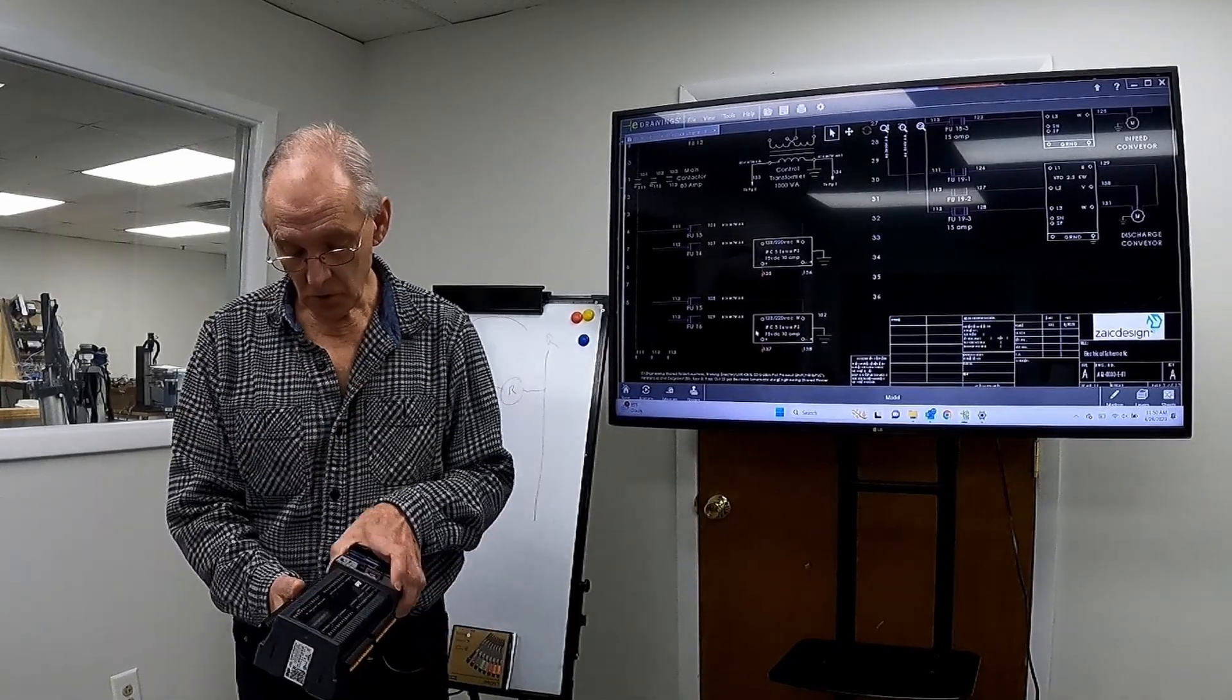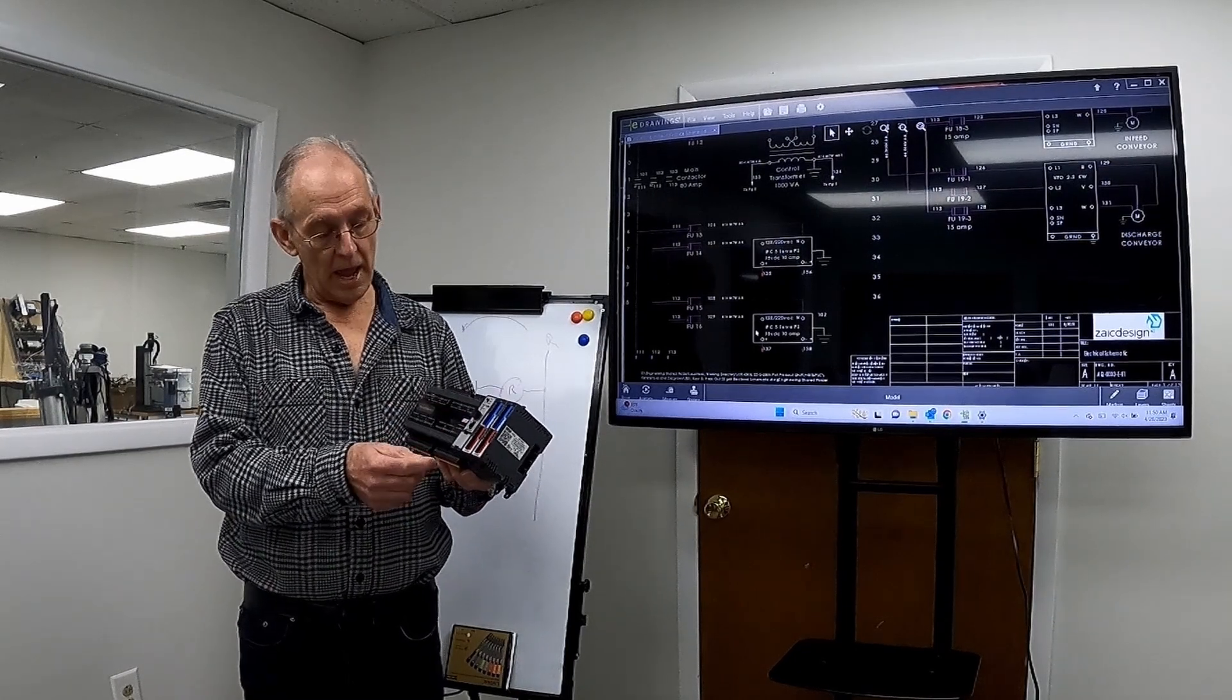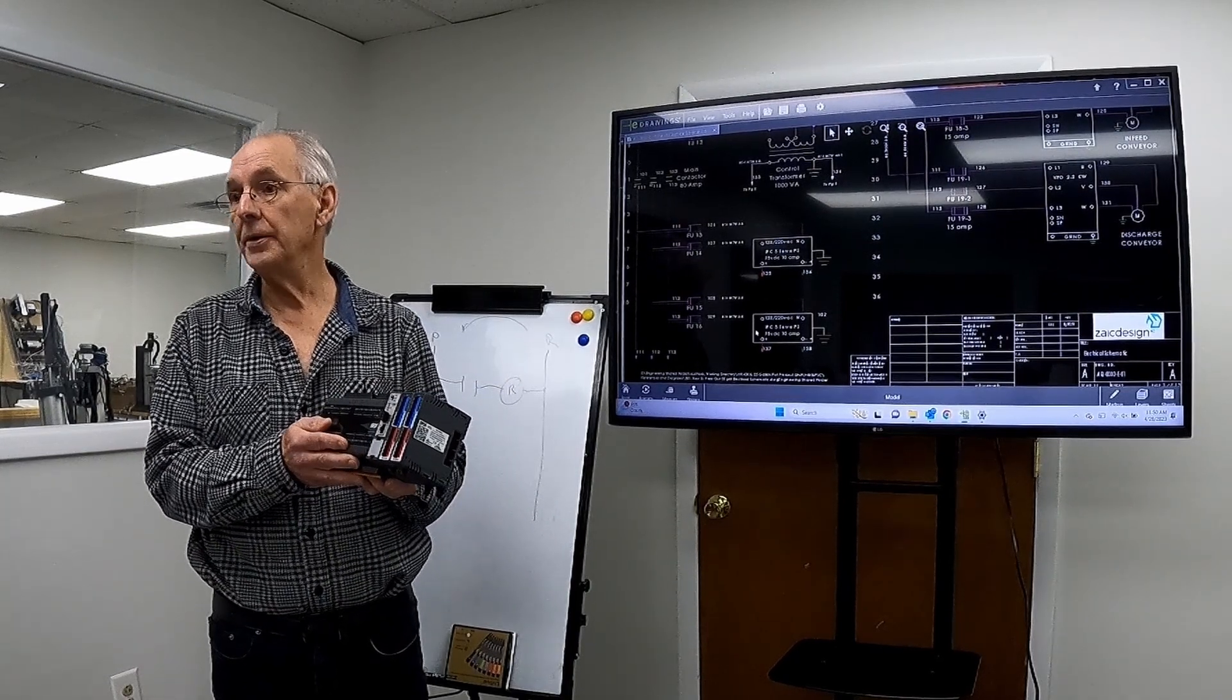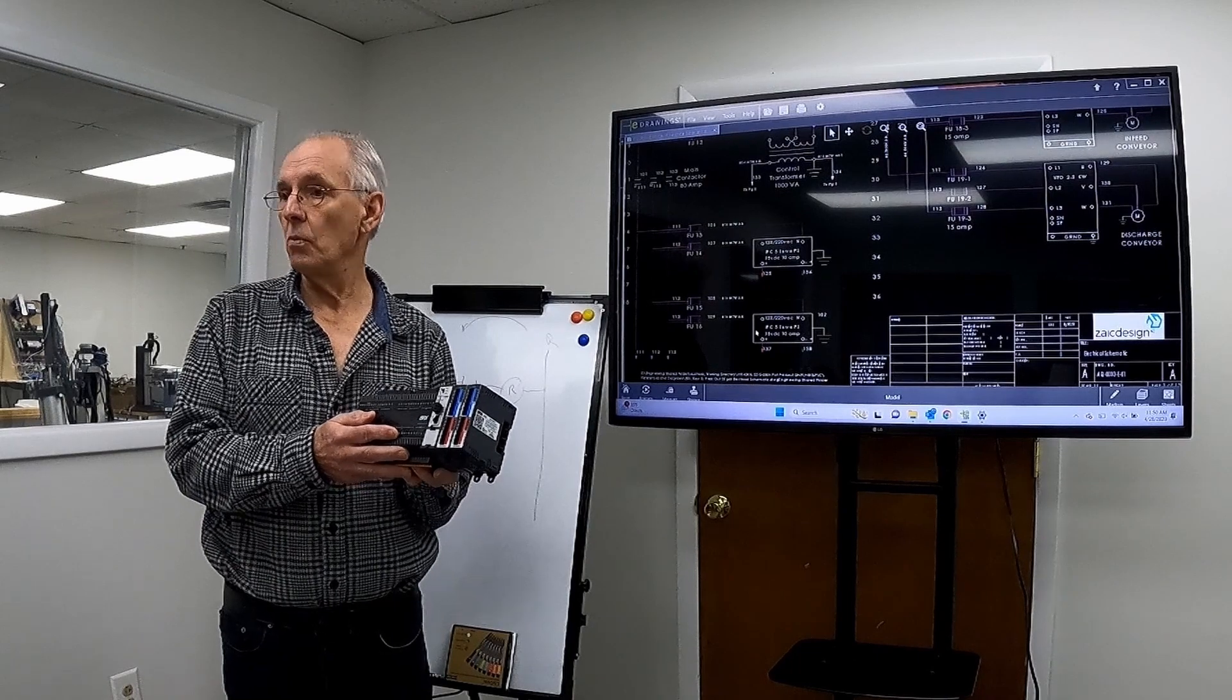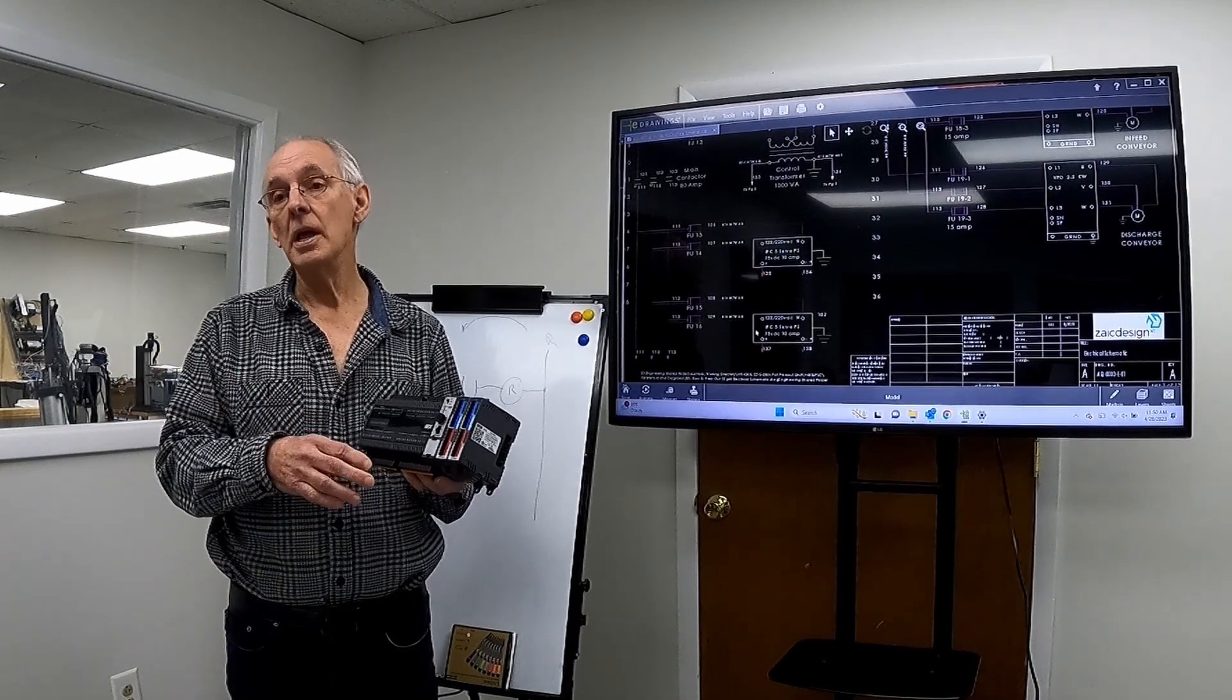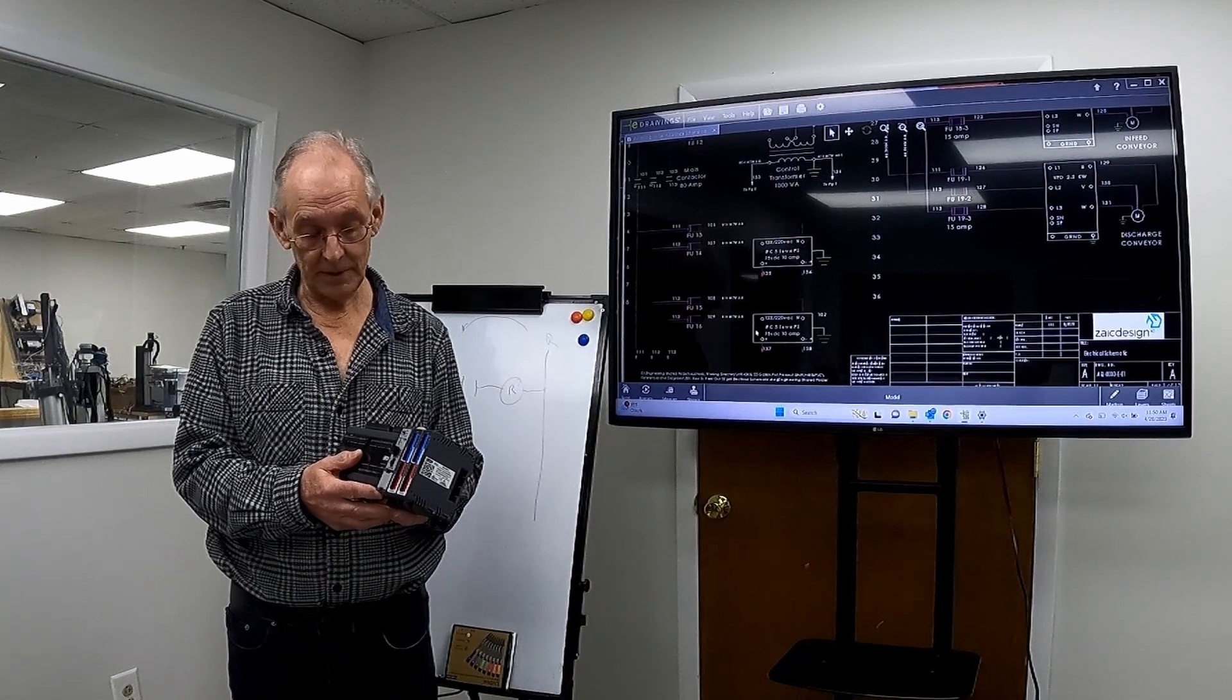Okay, so here's the PLC we're using, and there are inputs and outputs, and each one of them has - in the case of the inputs, we always leave the inputs on, right? And that's so that the machine, even though it's down and in an e-stop condition, I can see what is going on. I can see the position of the servos, I can see that doors are closed or open or whatever, and so I can troubleshoot. Without the inputs being on, troubleshooting would be impossible. You'd never be able to figure out why the e-stop is causing a problem, let's say.